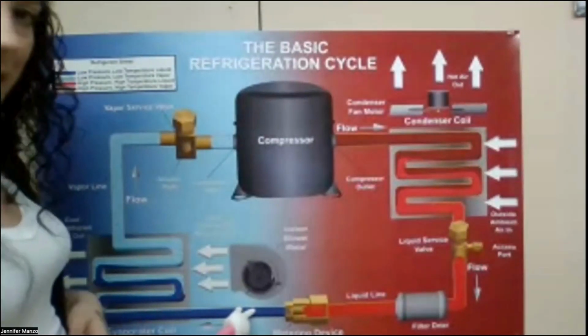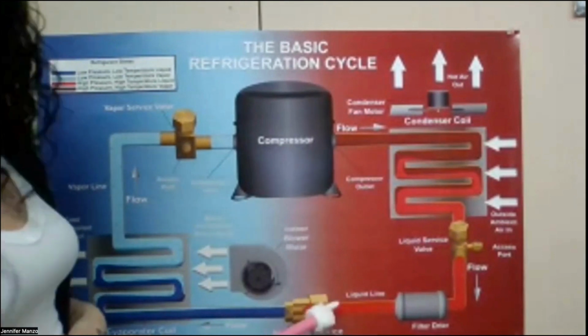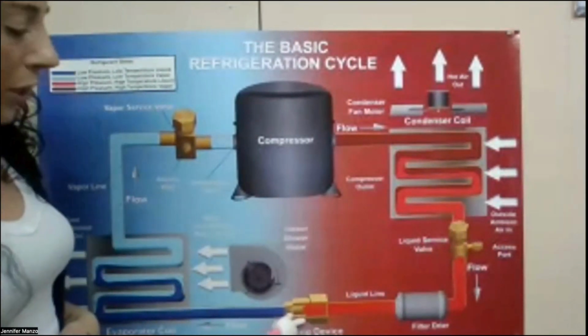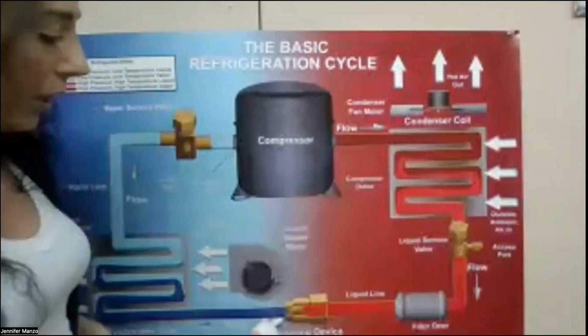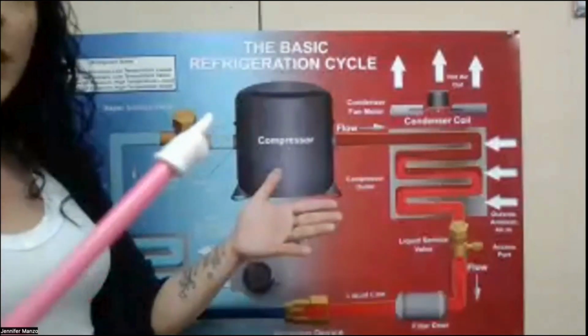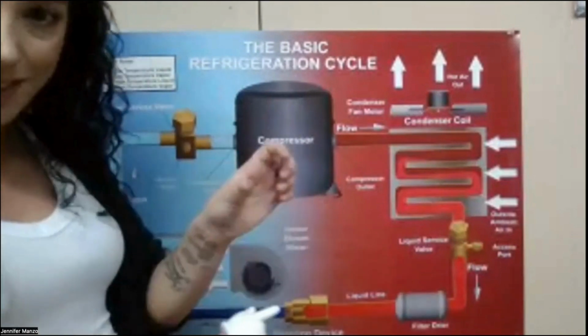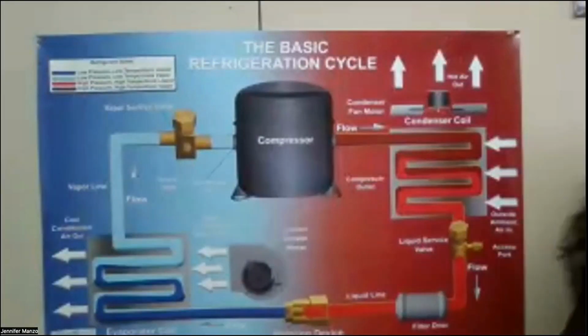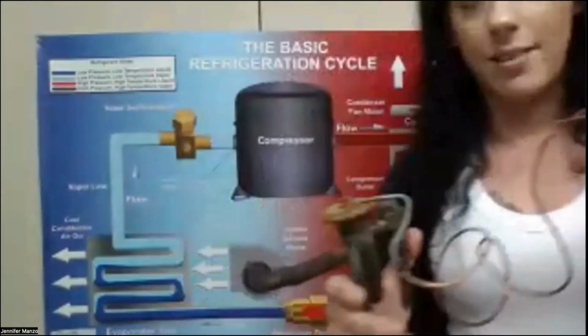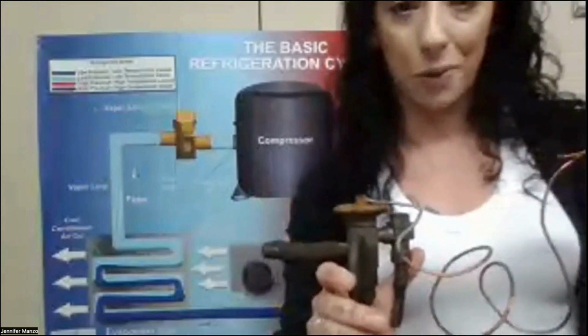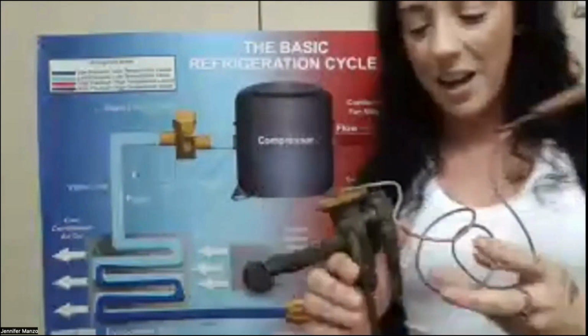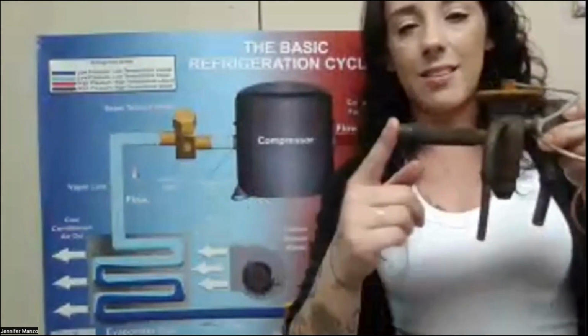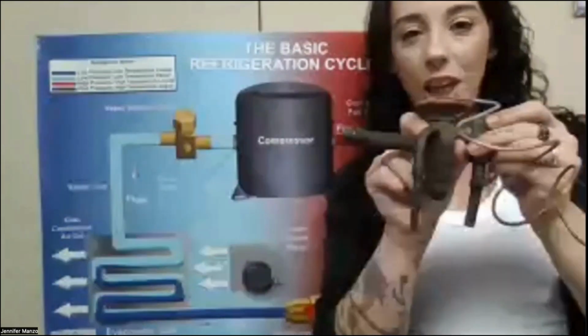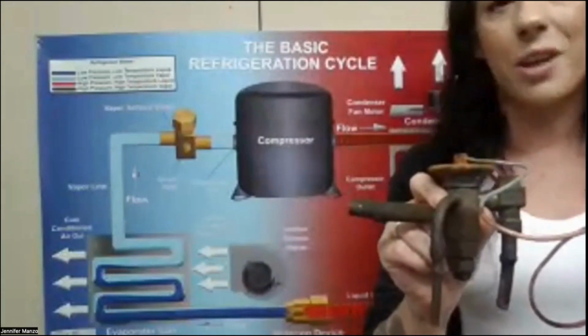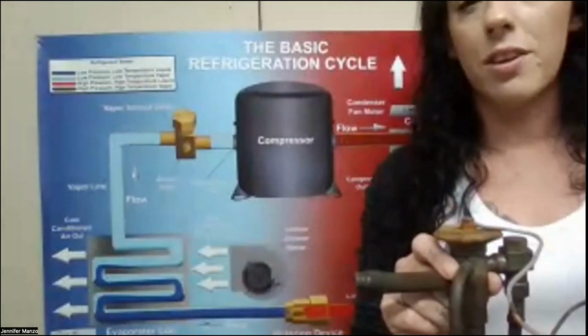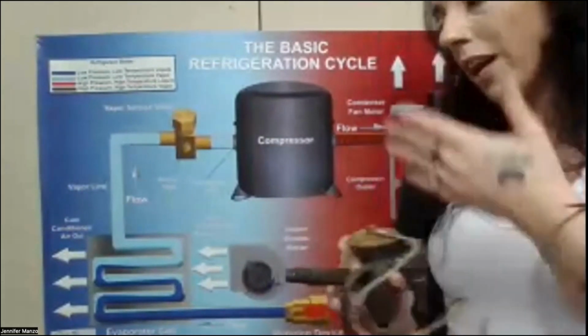You have a little bit of vapor in here. I know you guys can't probably see that, but when it enters the metering device, there's absolutely no vapor. It's 100% liquid. But when you leave the metering device, you are liquid, but you've got a little bit of leftover vapor just from the sheer change that is happening in such a small space. So you've got this big old unit. This TXV is actually off of a 10-ton lobster tank chiller, which is pretty insane, but it's the only one I had. So this tiny little thing, if you picture that this is the inlet, this is the outlet, right? You've got such a small space here to change the entire phase of this refrigerant. So because it happens in such a small space and there's just not a lot of leveling it can do, you get a little bit of vapor out the other side.